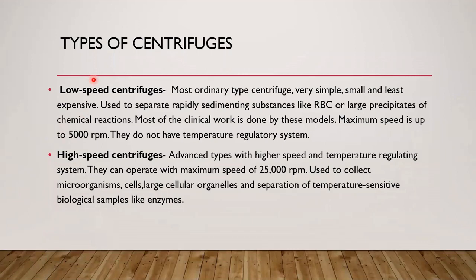The different types of centrifuges are: low speed centrifuges, high speed centrifuges, and ultracentrifuges. Low speed centrifuges are the most ordinary type — simple, small, and least expensive. They are used to separate rapidly sedimenting substances like red blood cells or large precipitates of chemical reactions. Most clinical work is done by these models. Their maximum speed is up to 5,000 RPM and they do not have a temperature control system.